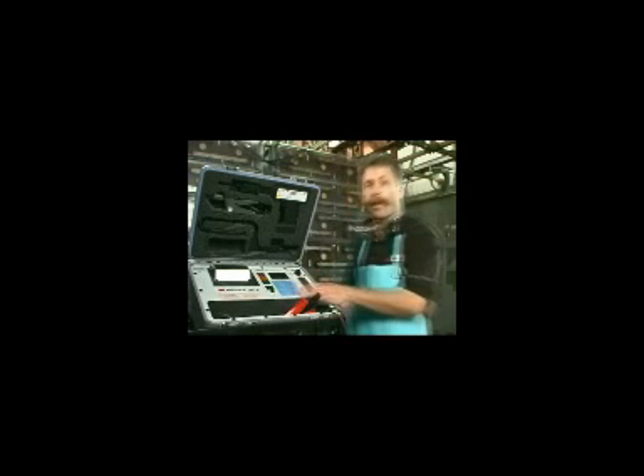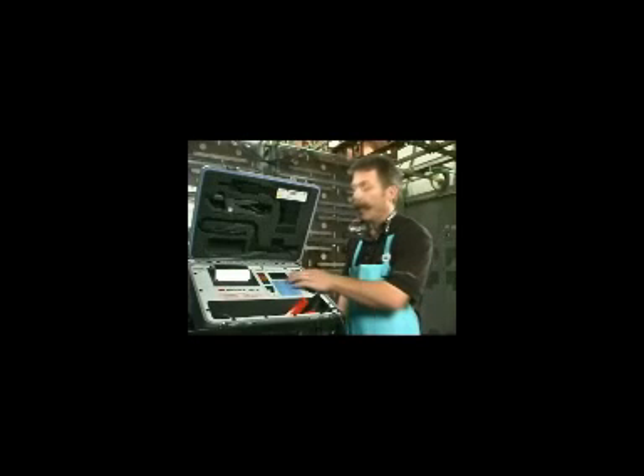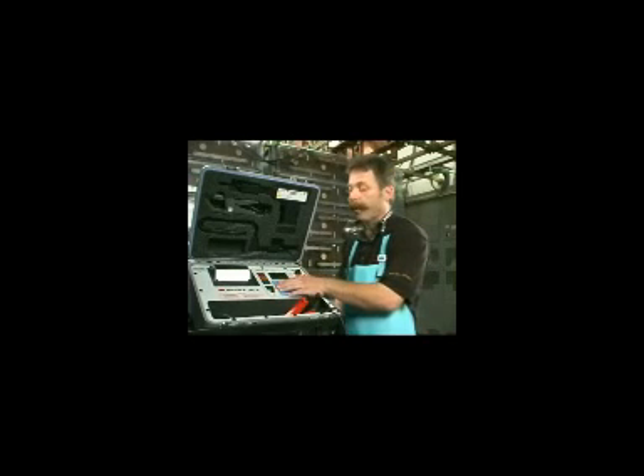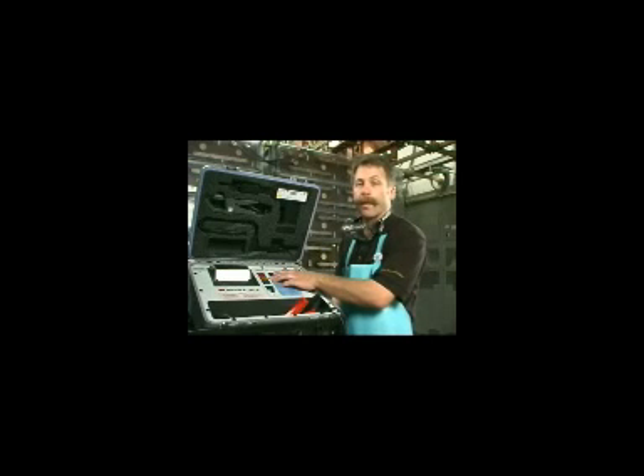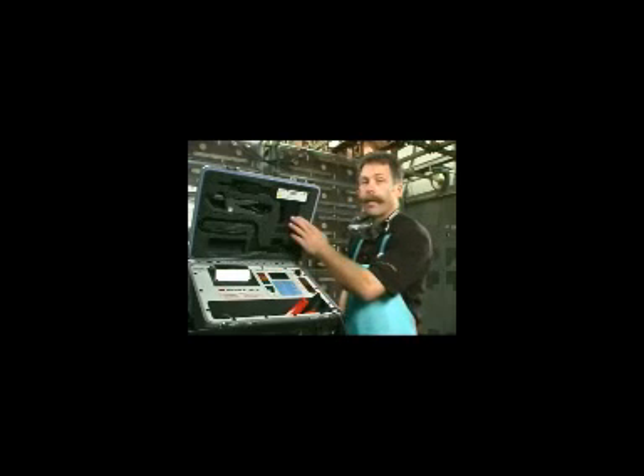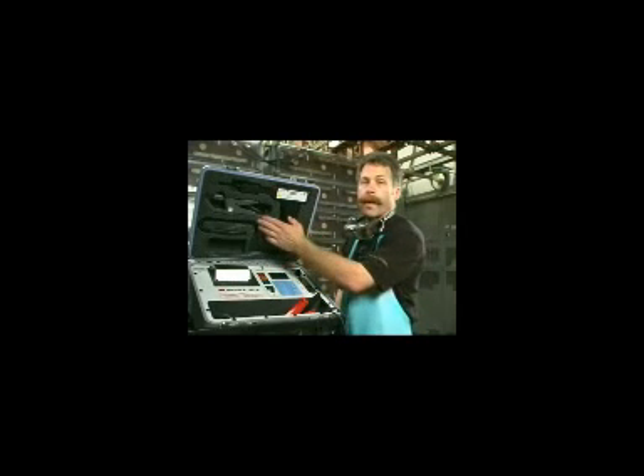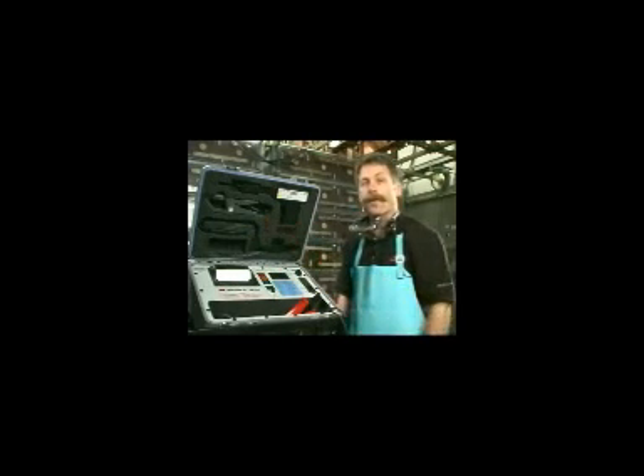What we have here is the transmitter portion with the input module, the current source lead connection, the meter that displays the current being applied to the battery, and various switches: the receiver battery switch, the current switch, the current ready light, and the overvoltage light. We also have the receiver, the potential probe, and the CT that are used to measure the internal impedance of the battery.